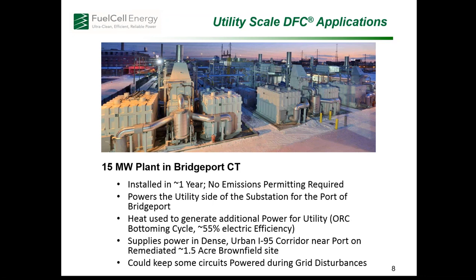The heat in this particular plant, since it's large and doesn't have an industrial host on site, is used through an ORC, an organic bottoming cycle, which generates additional electricity. That raises the electrical efficiency by turning available heat into additional electricity without any additional fuel requirements. It's supplying power in that dense urban I-95 corridor area right near the port in downtown Bridgeport.